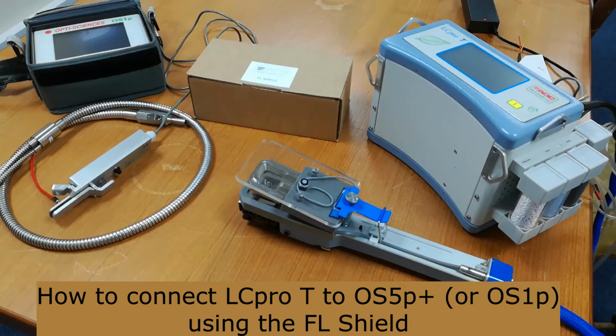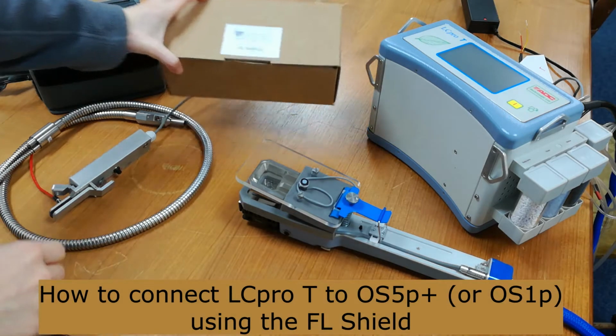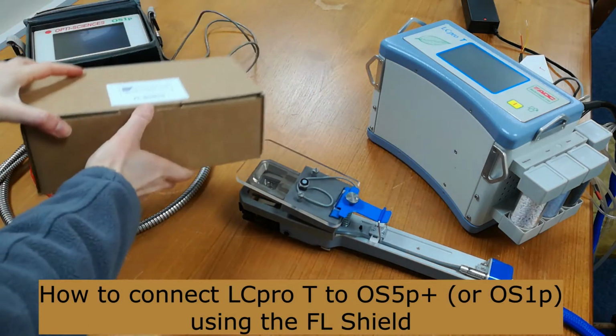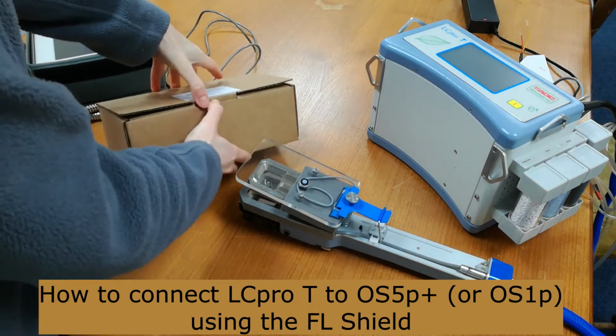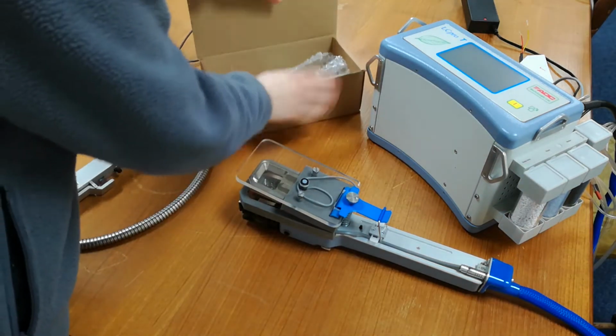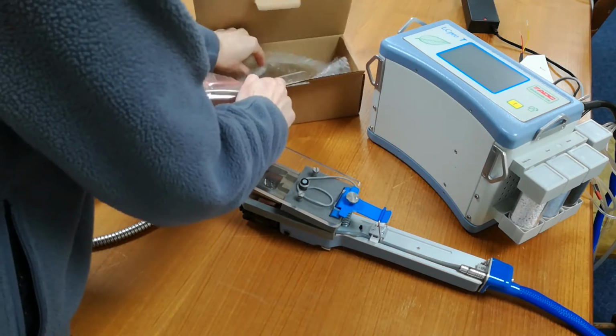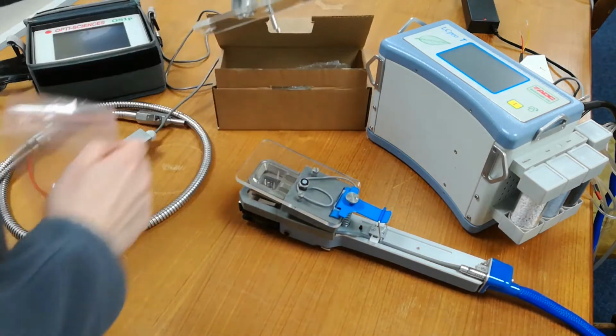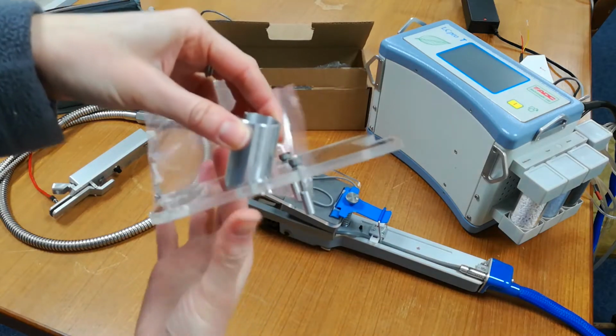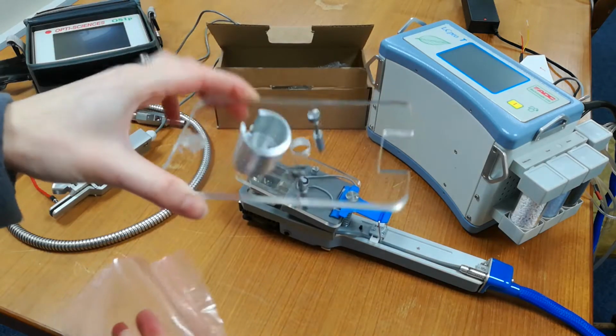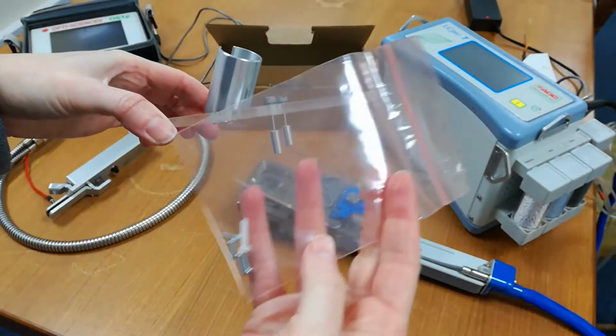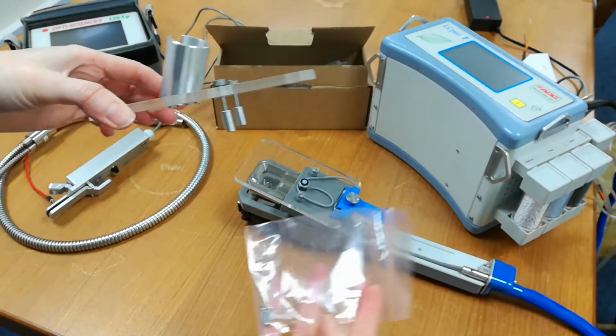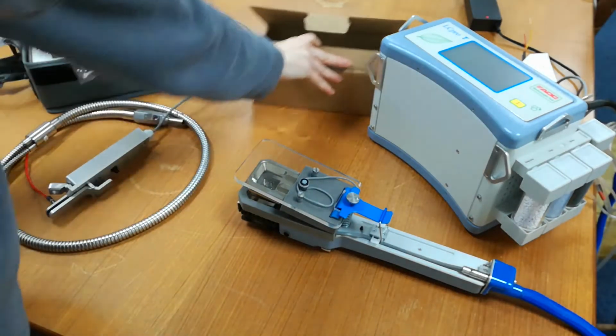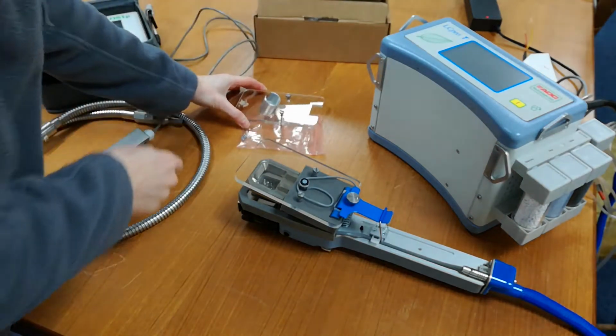How to connect the LCpro T to the OS5p Plus or to the OS1p using the FL Shield Fluorometer adapter. First, open the FL Shield box to find the fluorometer adapter and a small packet of spare screws. The 4 screws in the bag are used with the narrow leaf chamber. In this case, we do not need them and they can be stored in the FL Shield box.